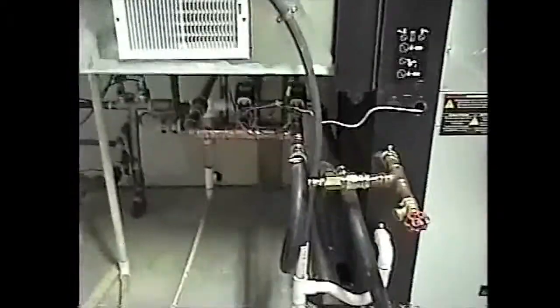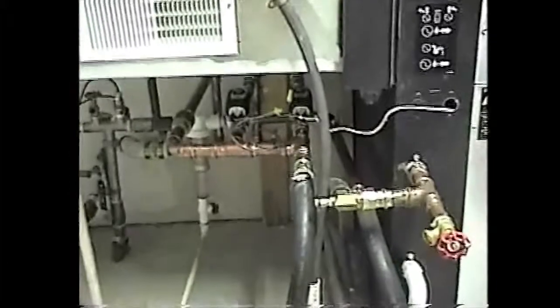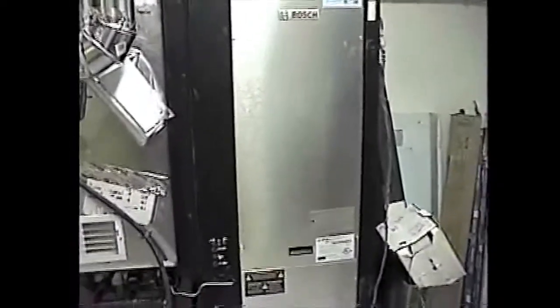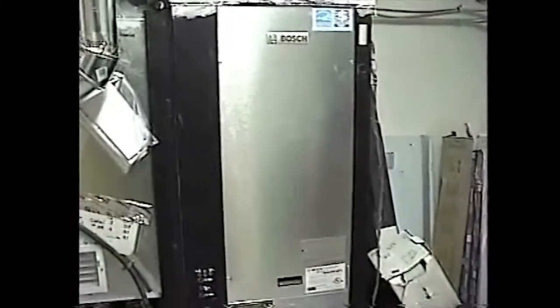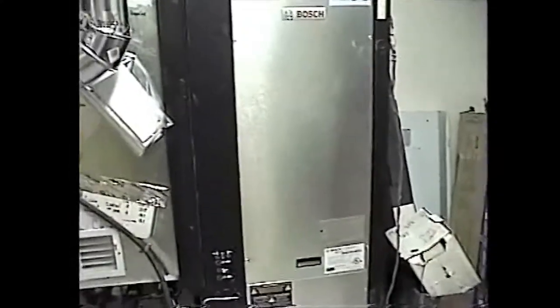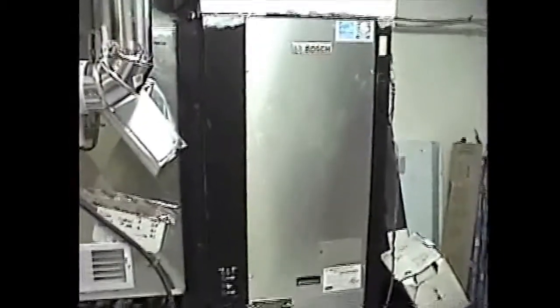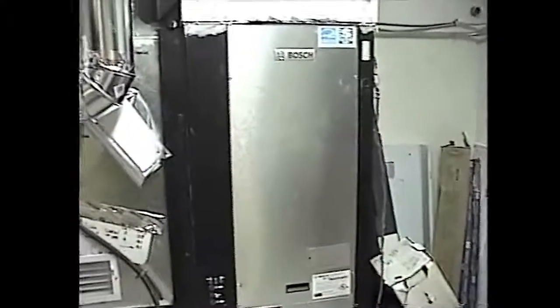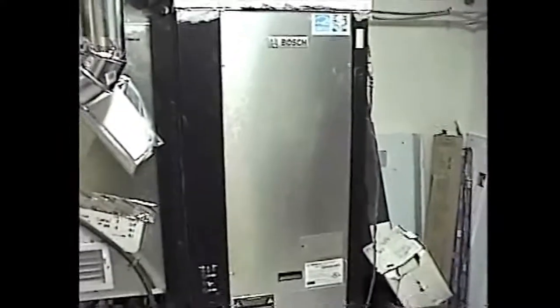There's a variable speed pump in the well. There's the monitor control for that. There's our 2-stage water valves underneath here for first and second stage. This is a 6-ton water source heat pump, a Bosch, and I'll show you the insides of it in just a minute. The control was an absolute snap to install. The only thing that takes a little bit more time than screwing on the older fan handler control is that it requires a motor change.